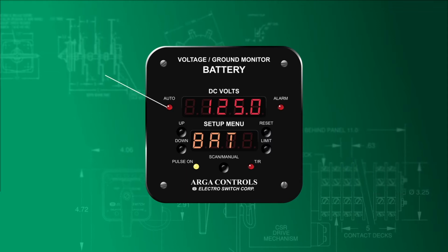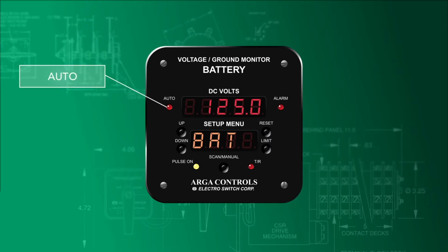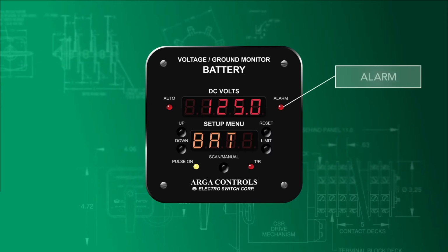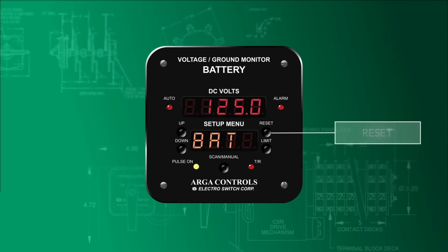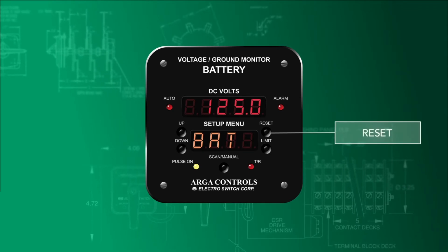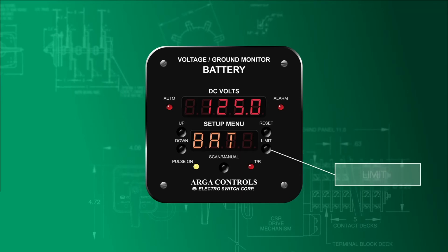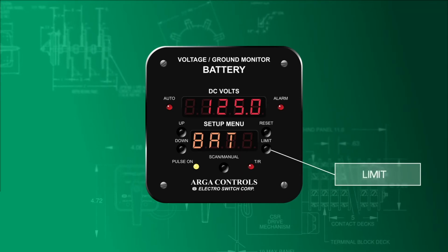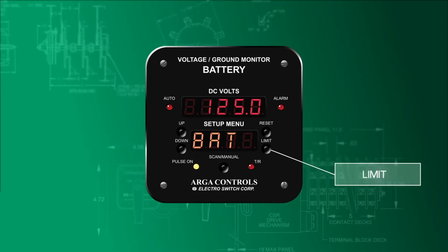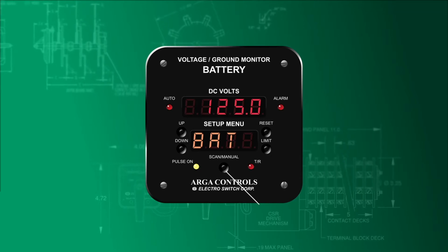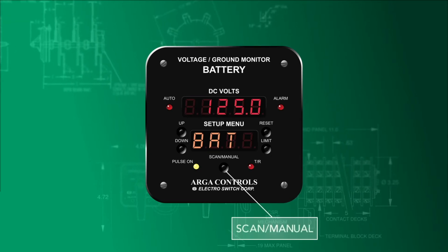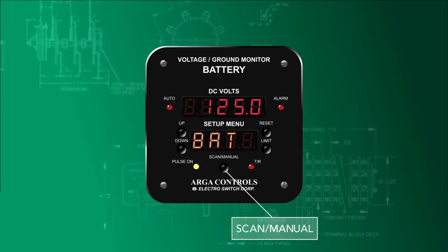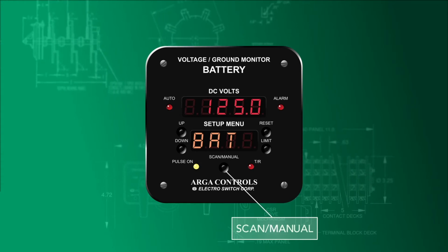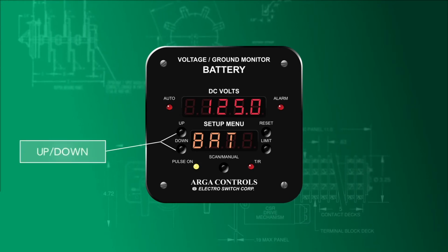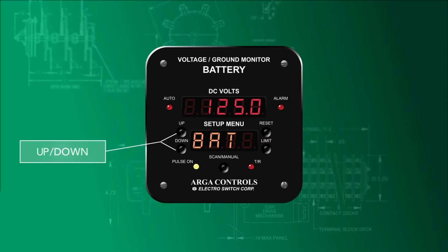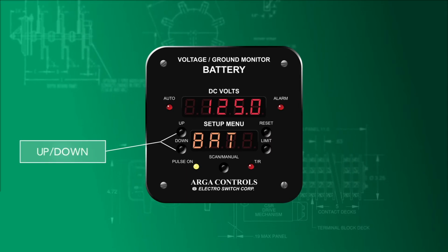You can see there is an auto LED indicator on the top left and an alarm indicator LED on the top right. There is a reset button underneath the alarm LED to reset alarms, a limit button to transfer between functional displays and also identify limits for specific values being displayed and monitored. A scan manual button is in the bottom center, which allows you to scan between various displays in the upper window. There are up-down buttons to the left of the setup menu to allow you to adjust limit set points to the end customer specific needs.